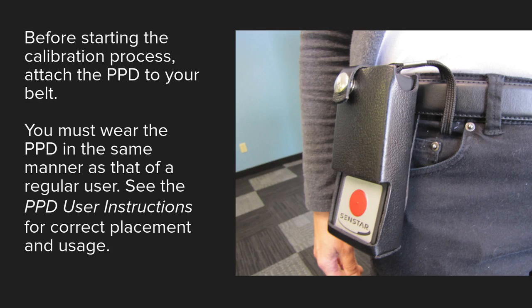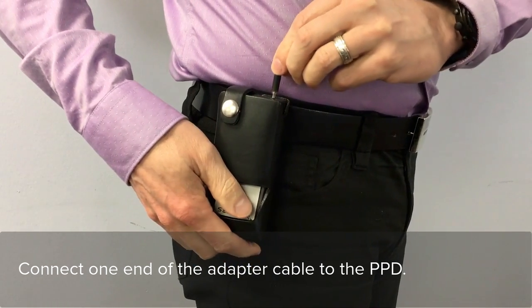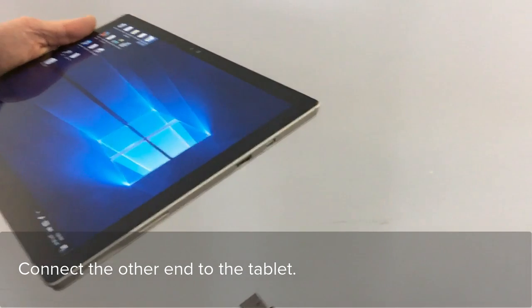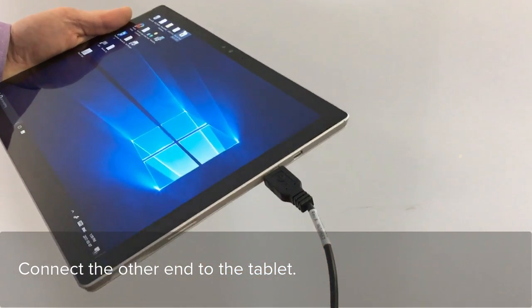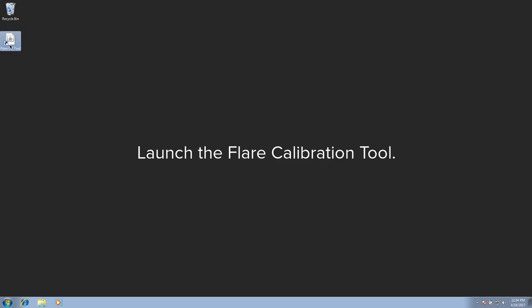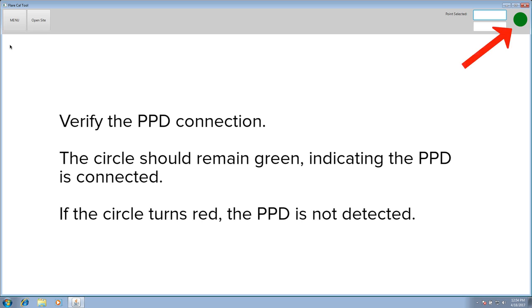Before starting the calibration process, attach the PPD to your belt. You must wear the PPD in the same manner as that of a regular user. See the PPD user instructions for correct placement and usage. Connect one end of the adapter cable to the PPD. Connect the other end to the tablet. Launch the Flare Calibration Tool. Verify the PPD connection. The circle should remain green, indicating the PPD is connected. If the circle turns red, the PPD is not detected.